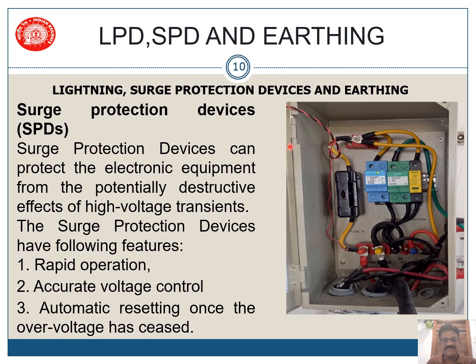Surge protection devices can protect electronic equipment from the potentially destructive effects of high voltage transient currents. The features of this SPD are rapid operation, I said it will be in nanoseconds, accurate voltage control, and automatic resetting once the over voltage has ceased. So heavy current आया तो ये protect करेगा. This will protect, and when the current is not available, subside हो गया तो automatically reset हो जाएगा. That is the specialty of your SPDs or LPDs that are provided in the system.